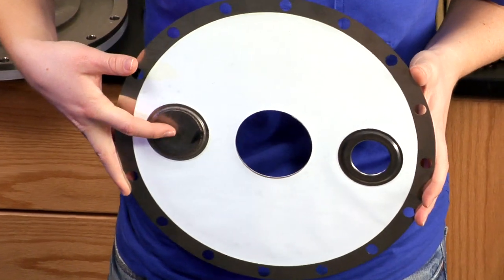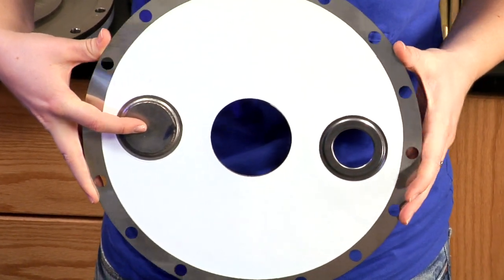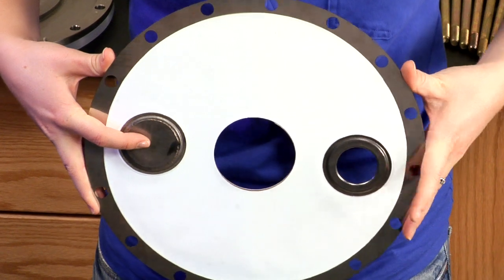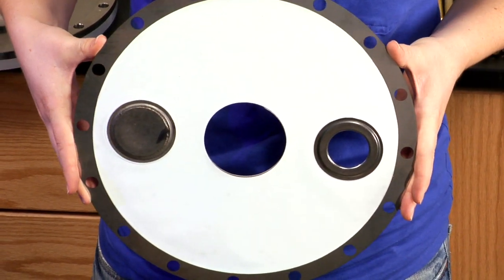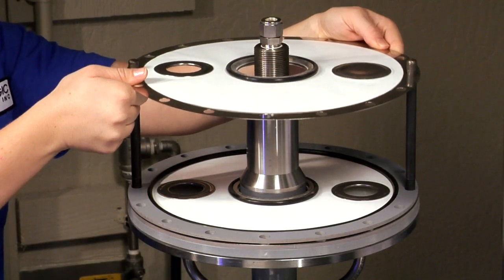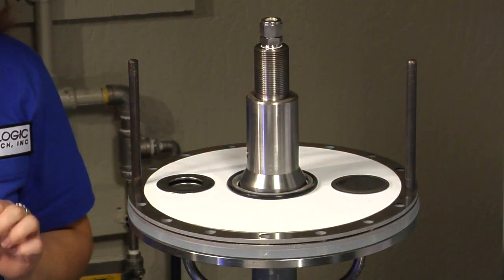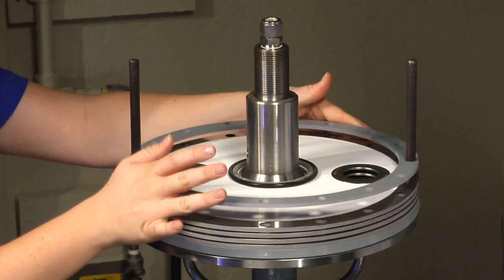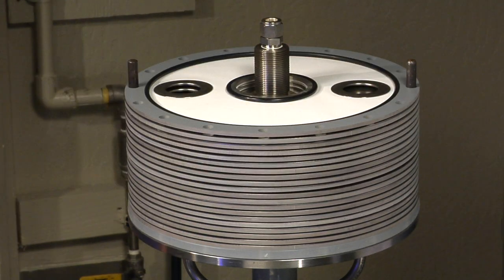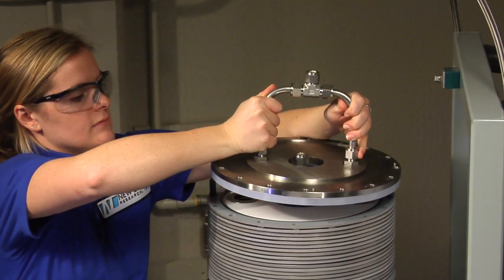The next tray installed will be a diverter tray with a plugged grommet. These will alternate every other tray and every other diverter tray will alternate the grommet position from three o'clock to nine o'clock. We'll continue to repeat this procedure until we have installed all 19 trays. Your filter pack is now fully assembled and ready for use.